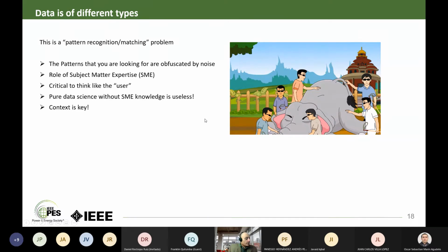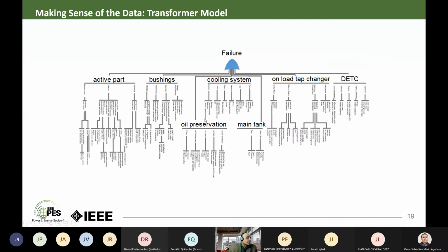Keep that in mind as we go into the next picture here. This can become very complicated. If I'm looking at the transformer model, there are active parts, bushings, a cooling system, a tap changer (of course, not for all transformers), dielectric-related parts, oil preservation, main tank. Each one of these has multiple parameters. So if I'm now looking at it, each of these parameters has a stream of data that goes with it, and each of these data elements can be at different frequencies and different granularity.